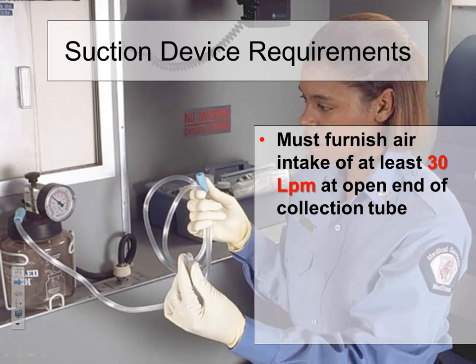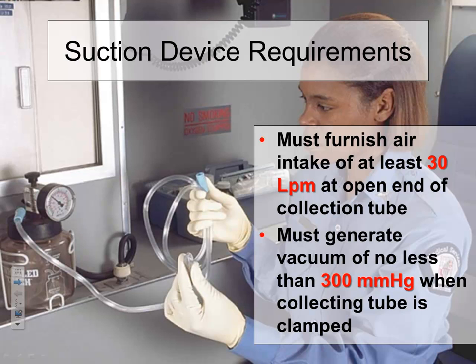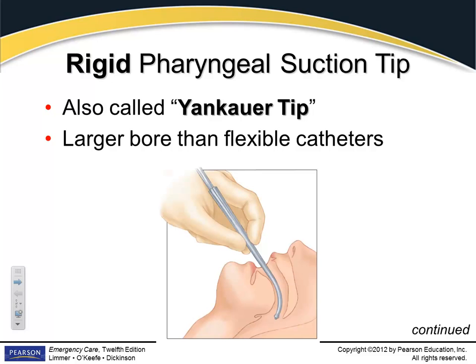Your suction device must have an air intake of at least 30 liters per minute at the open end of the collection tube. So that means without that suction point on there, if you were testing that, it's got to be sucking at least 30 liters per minute. So it needs to be a pretty serious suction. It's got to generate a vacuum of at least 300 millimeters of mercury. So when you clamp that tube down, the suction pressure that builds up in there should be at least 300 millimeters of mercury. So that's quite a bit.